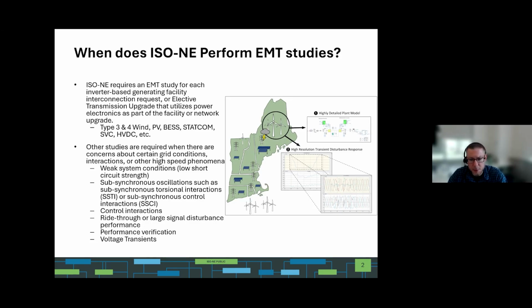Other times we run these studies outside of interconnection space: our operations group has recently started taking up some of these studies as well, looking for things like weak system conditions, subsynchronous oscillations, control interactions, and general ride-through. The idea is that EMT models have higher fidelity than positive sequence models, and that phenomena can be really important to understand as more and more of these sources come onto the grid.